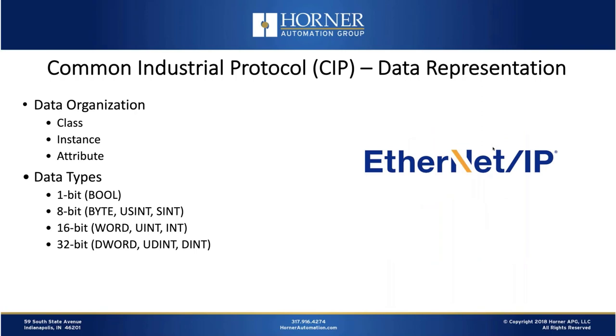To call out a specific piece of data in a CIP device, you really need to know the class, instance, and attribute for that piece of data. Whereas Modbus was designed around word-type and bit-type data exclusively, Ethernet IP and CIP support a wide range of data types ranging from 1-bit to 32-bit — at least 10 different types — so it's a much more modern data handling approach.